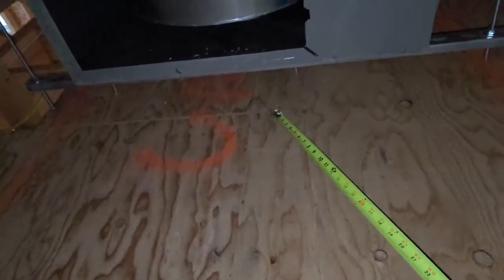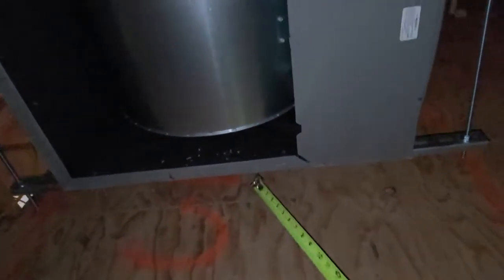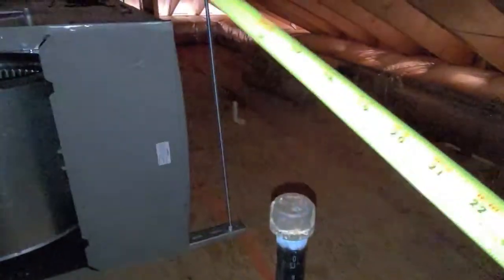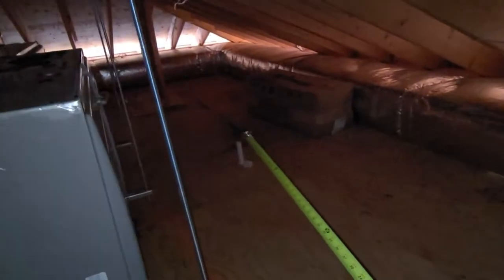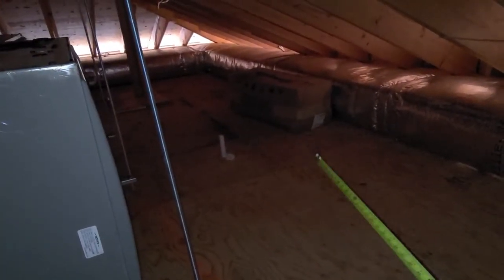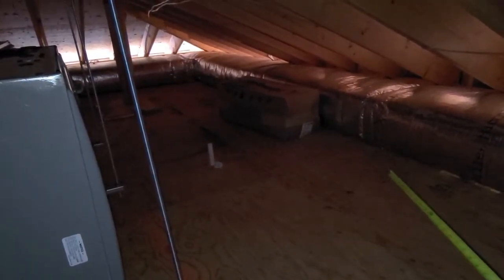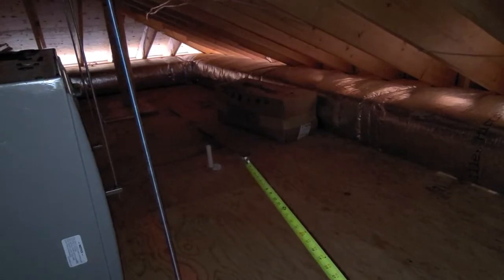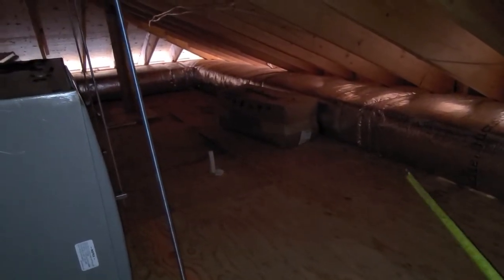So when you look at the unit, we are missing something. Usually they have an emergency pan in case of a leak or anything. He didn't install it yet, it's not done. But we have, of course, a gas pipe over there. You need to make sure you have the drain installed. Now this drain, he has to take it to another waste line or take it to the basement. So he's going to run it inside the wall. Make sure this drain is at least brought up to the attic, so he doesn't have to open walls after we close it.